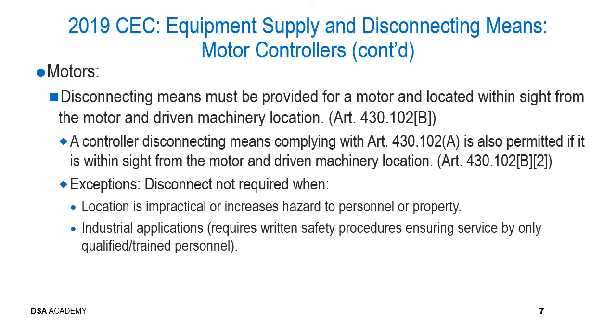Now, when we're talking about just motors, not motor controllers, but motors, the requirement in Article 430.102(b) clarifies that a disconnecting means must be provided for a motor and located within sight from the motor and driven machinery location. It goes on to say that a controller disconnecting means complying with Article 430.102(a) is also permitted if it is within sight from the motor and driven machinery location, based on Article 430.102(b)(2). So a lot of the exceptions that we just discussed may be applicable to a motor if the controller disconnecting means complies with what we just discussed.